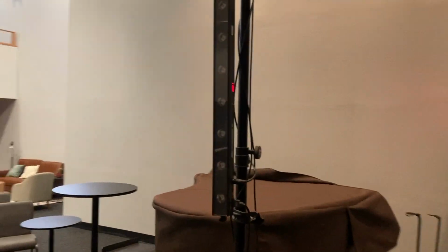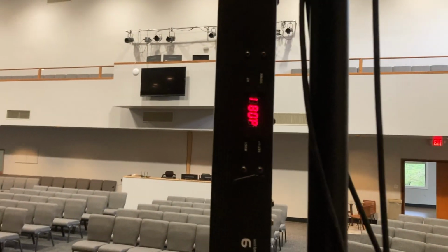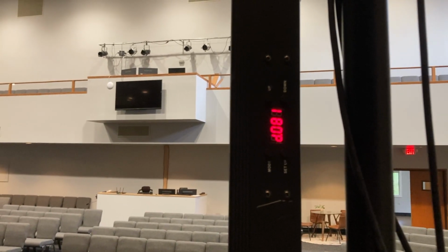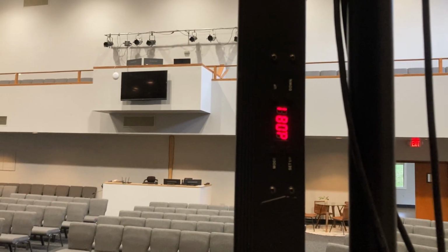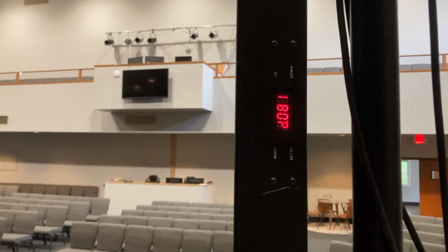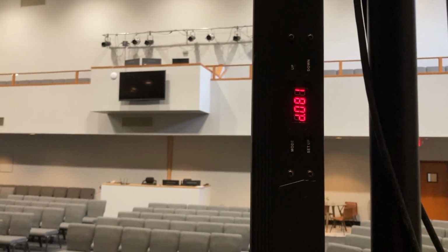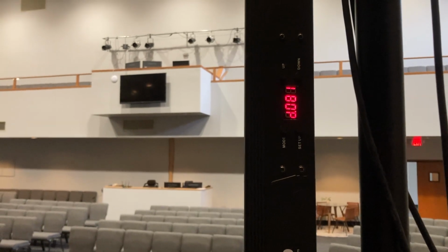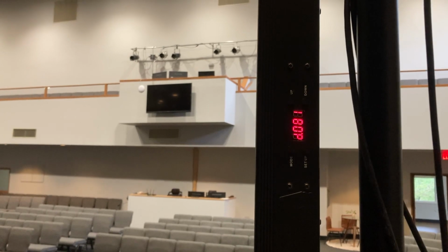On each light, you can adjust the settings right here with those buttons. And so you can see you have mode, setup, up and down. If it doesn't start with a D and then the 081 or 065 or something like that, if it doesn't start with the D, then that means it's not set to DMX mode. So someone else has changed it, and you want to make sure that it's set to DMX mode, otherwise it will not receive the proper signal from the iPad.